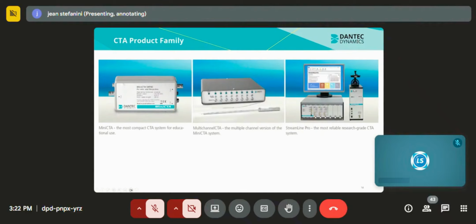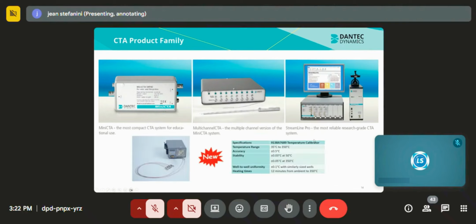One of the things that is very important to keep in mind is that all these devices need a calibration. This is why we have developed a calibration unit here, where we control the flow, we change the flow, and then we measure the voltage and create this calibration curve. They can be used for 1D, 2D, or 3D. Same for calibration. I mentioned the possibility to measure temperature fluctuation as well. We also recently developed a calibrator for temperature measurements that can be used to calibrate your probe when you have temperature fluctuation. So this is a point measurement technique. You measure at a very specific location. And this is an intrusive technique because you insert something into the flow.